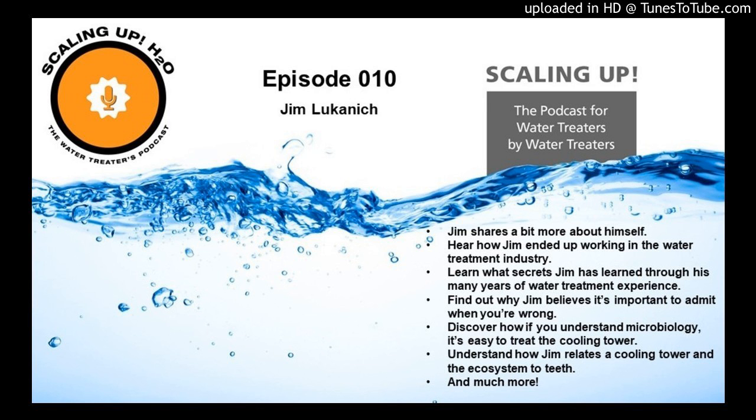In my opinion, I don't know why they even sell pot feeders, because they don't have a filter in them. If you don't have a filter on your closed loop, I don't understand why, because that's one of the four areas that we have to treat. And as I said before, our job is to be a heat transfer efficiency manager. And if we've got a bunch of dirt and debris on the side of our heat transfer surfaces, we're not doing a very good job of that. Why not take out that pot feeder and replace it with a filter feeder? That way we're taking out all the crud that's in the system.